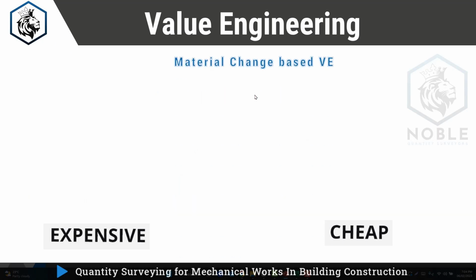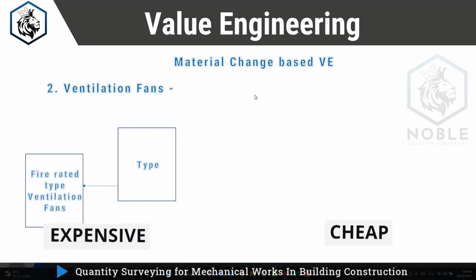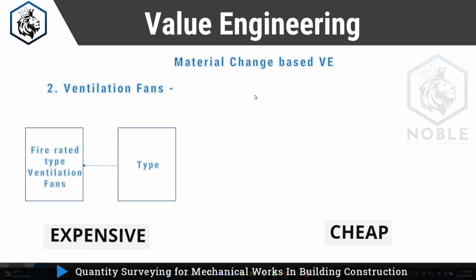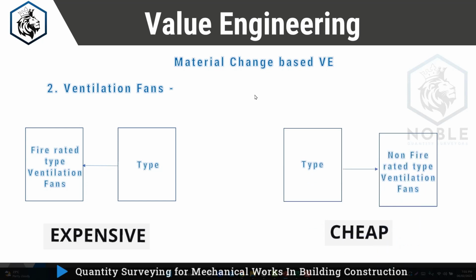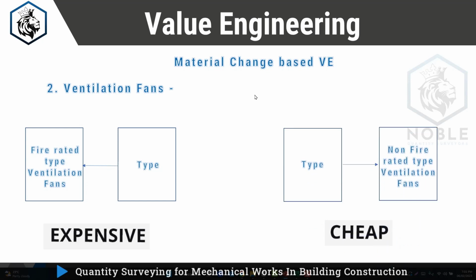Next, in material change based value engineering, your ventilation fans. The expensive options are fire rated type ventilation fans or smoke fans, generally used for fire rated types, but sometimes the specification asks for ventilation fans also to be fire rated type. This is expensive, and if you change it to non fire rated type ventilation fans, it becomes a cheaper option, with a difference of almost 10 to 15% in this value engineering.